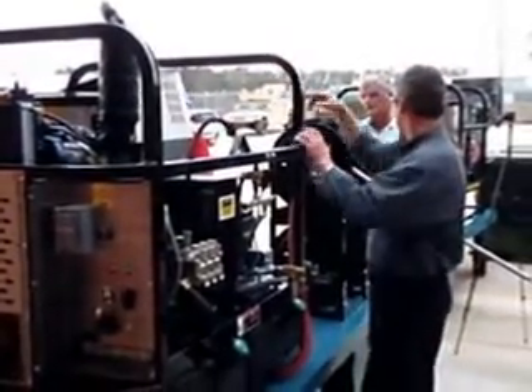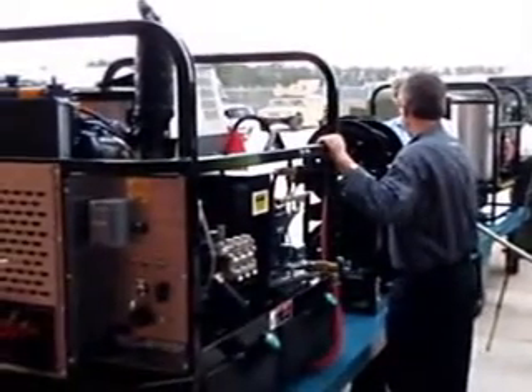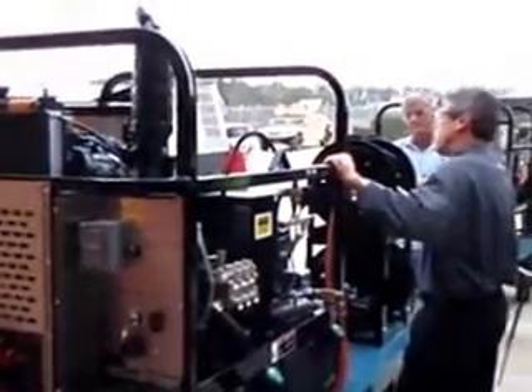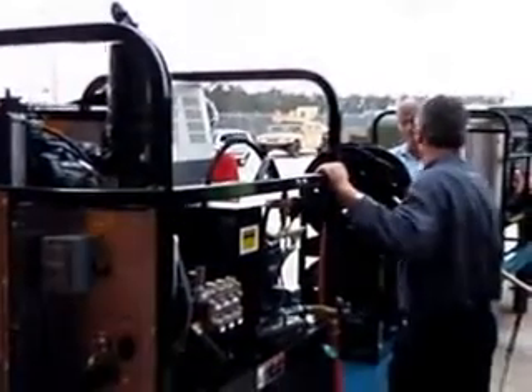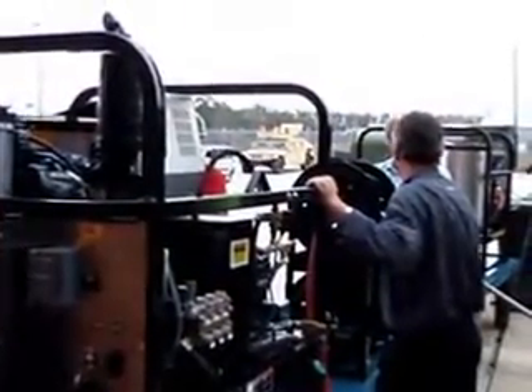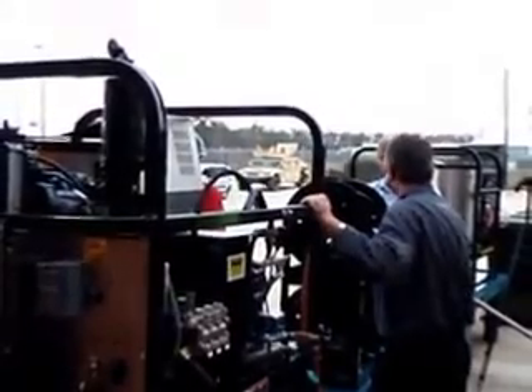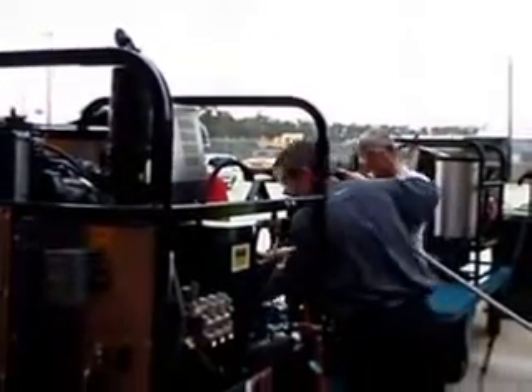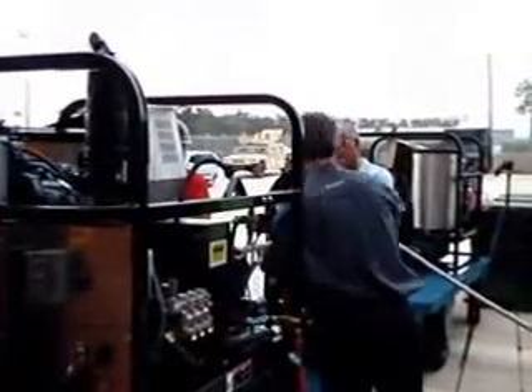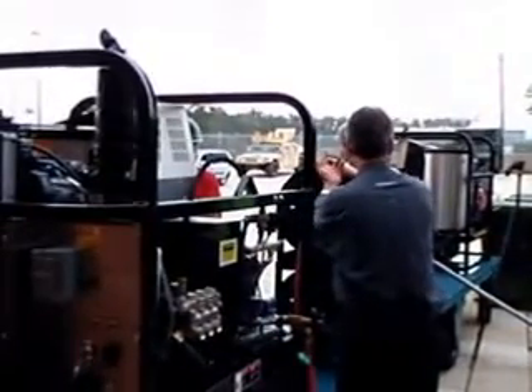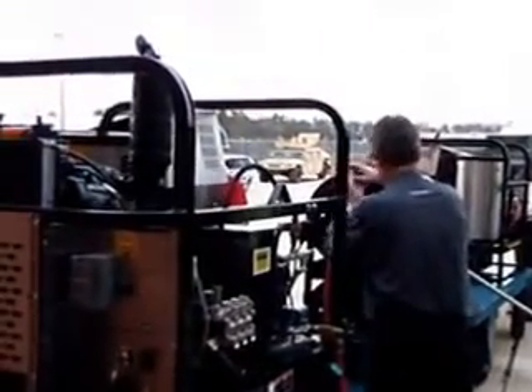Now, how often does that plug up when it doesn't have to be plugged in? That's a good question. It depends on the fuel being used, primarily. Your burner system, the way it burns, the cleanliness of the burn is based on two things: your fuel and your air mixture, and the cleanliness of your fuel. Those are the things it's dependent upon.